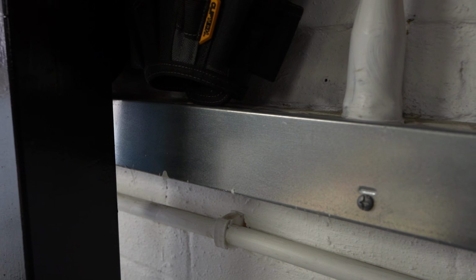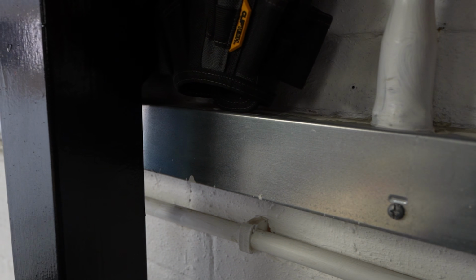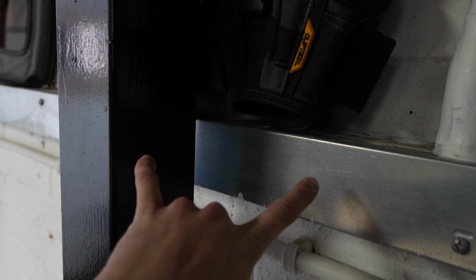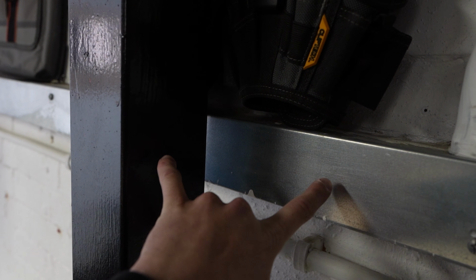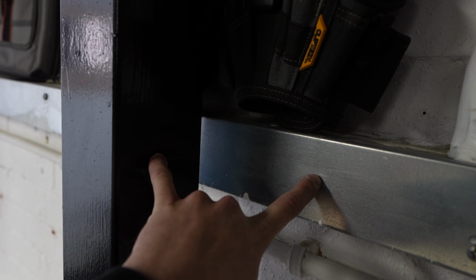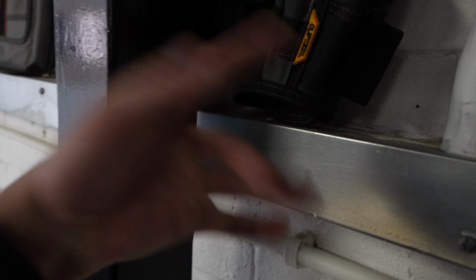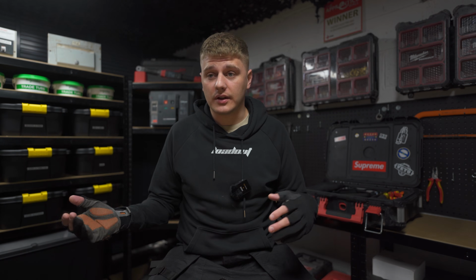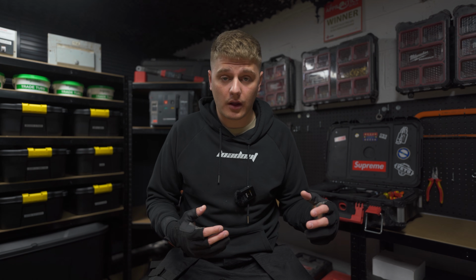So yeah, that potential is going to be different to, of course, the potential under fault conditions inside the building. So if you were to touch some of the pipe work and an exposed conductive part of the installation at the same time, there's going to be a potential difference there, which is voltage, and that voltage is going to allow current to flow to earth, killing you in the process.